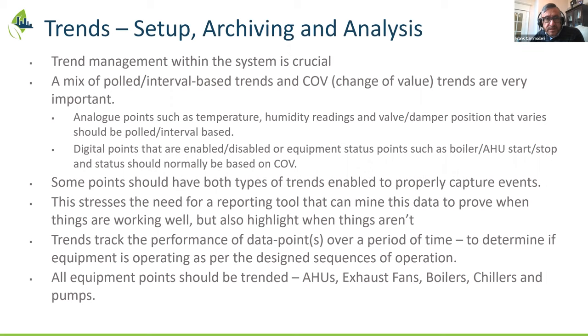Just a little bit about trends for those not familiar with the different types that exist. Basically there's a mix of them. There are interval-based trends, such as analog points like temperature and humidity, polled every 5, 10, or 15 minutes. 15 minutes seems to be the standard, and it's important that when they get set up with that interval in place, you don't want anything less than or more than 15 minutes. If you have hourly readings, you don't get into the granularity you need, and sometimes you need even 5 minute intervals. Then there are digital points, which enable things coming on and off or scheduling, and we'll show an example shortly of a combination of these items.